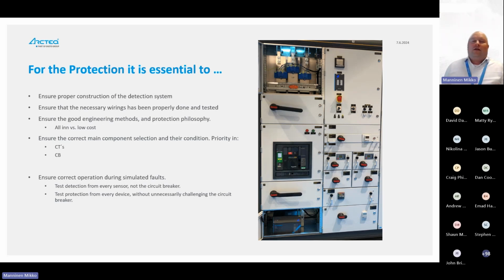Let's say that the big project has, for example, 120 or 200 sensors. You don't want to trip the circuit breaker 200 times. It's not really necessary. The circuit breaker should be tripped probably one time from each relay, but not from each sensor. It's essential that the circuit breaker will be tested and left in a very good condition, able to make the protection. We don't want to challenge the breaker too much.